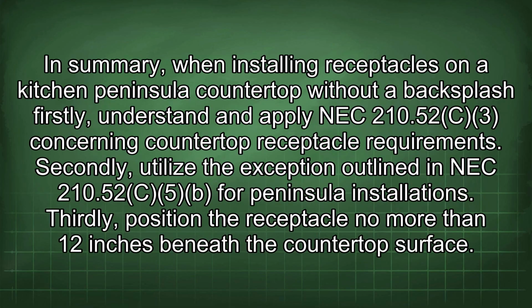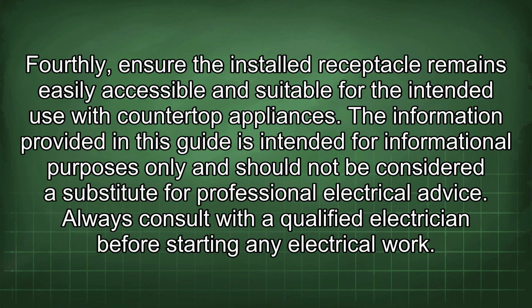In summary, when installing receptacles on a kitchen peninsula countertop without a backsplash, firstly, understand and apply NEC 210.52(C)(3) concerning countertop receptacle requirements. Secondly, utilize the exception outlined in NEC 210.52(C)(5) for peninsula installations. Thirdly, position the receptacle no more than 12 inches beneath the countertop surface. Fourthly, ensure the installed receptacle remains easily accessible and suitable for the intended use with countertop appliances.